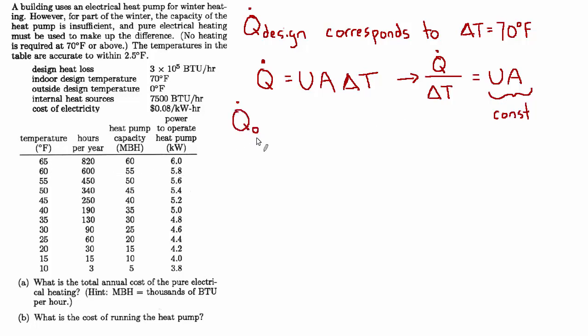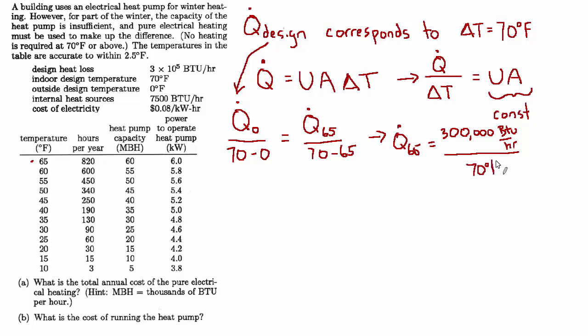We'll divide by delta T on both sides, and say the heat loss divided by the delta T is equal to the overall heat transfer coefficient times the area. And what's interesting about this is the overall heat transfer coefficient is a function of that building. It has some walls, some windows, and a roof, and it's made of particular materials. So that's roughly constant. And the area is also constant. The building isn't changing throughout the seasons. So this product is a constant.